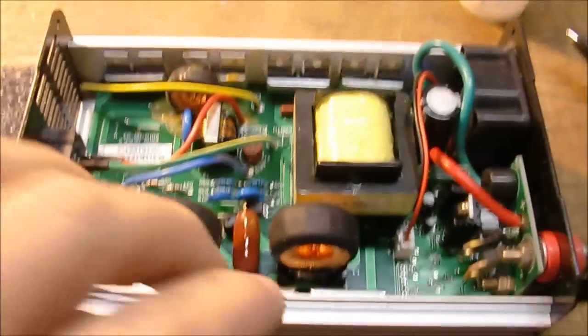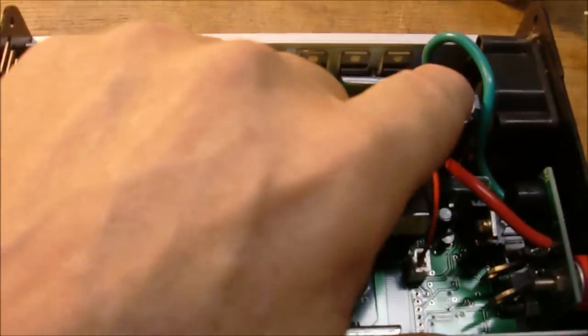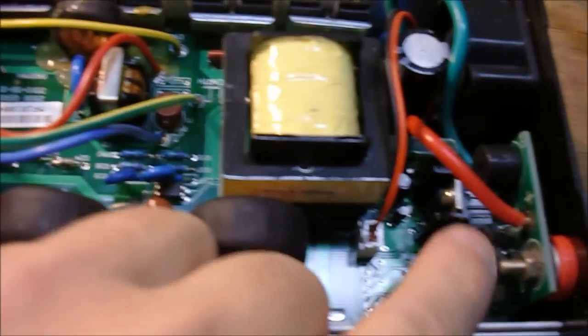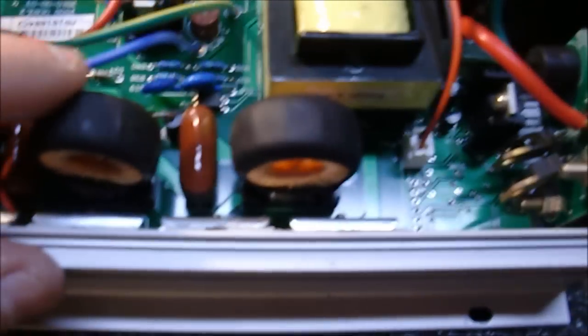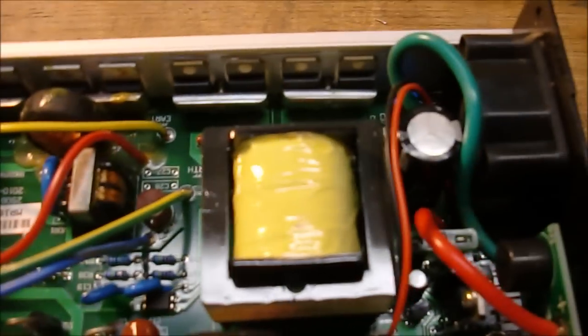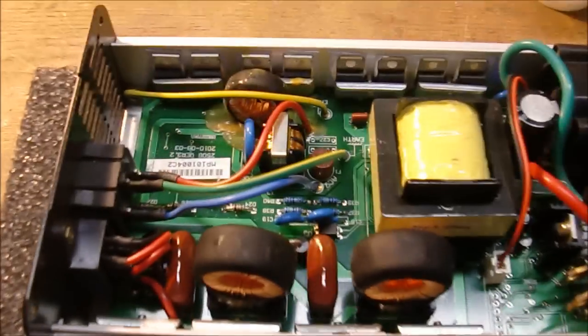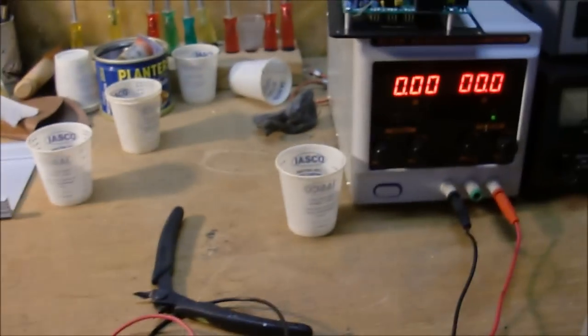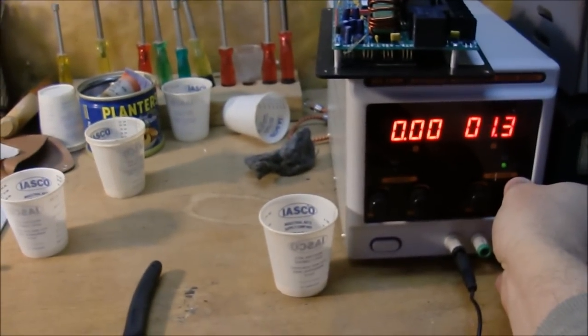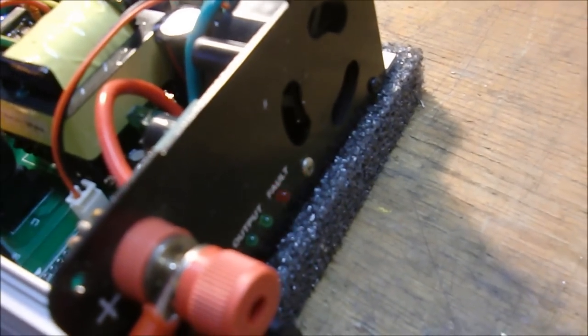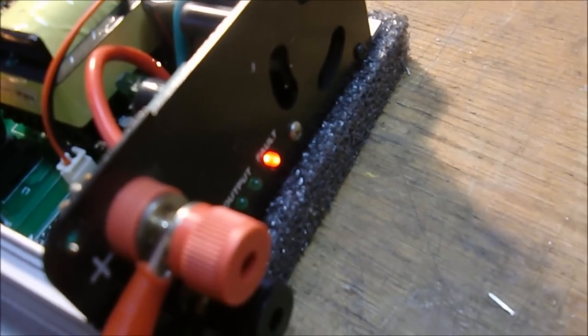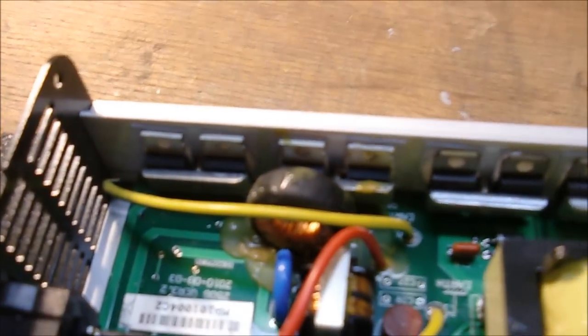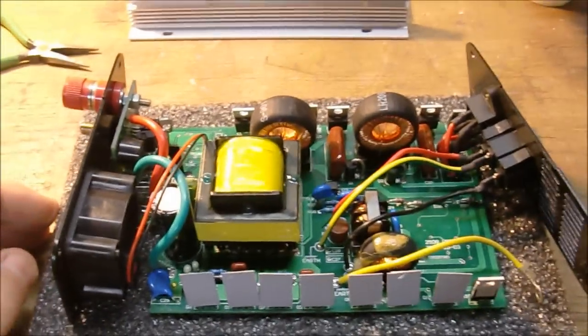Here's another one, got it opened up. The capacitor looks good. Everything looks good on these. They're all built about the same time it looks like. Got it all connected. I'll crank this up, look at my lights here. Red light comes on about seven. Get up to 12, stays on steady. No boogie lights. Probably the same thing, that AC fuse down there and one of those MOSFETs.